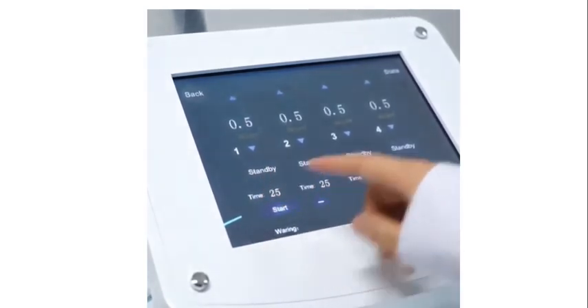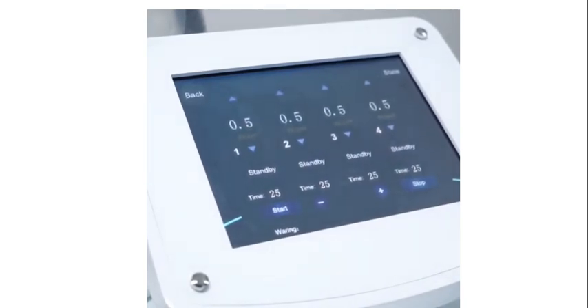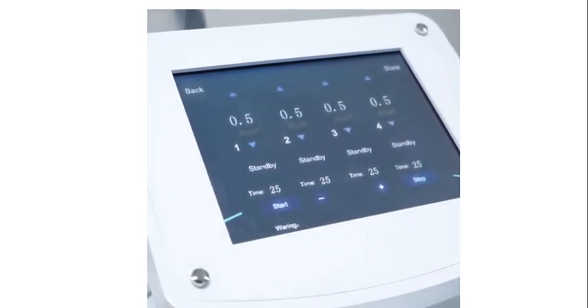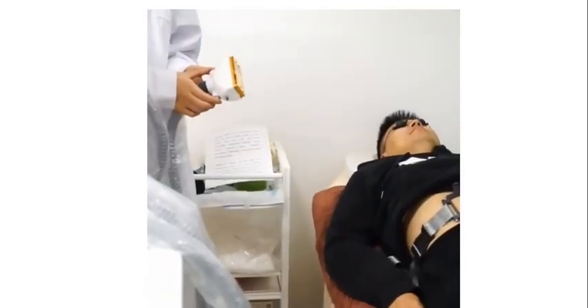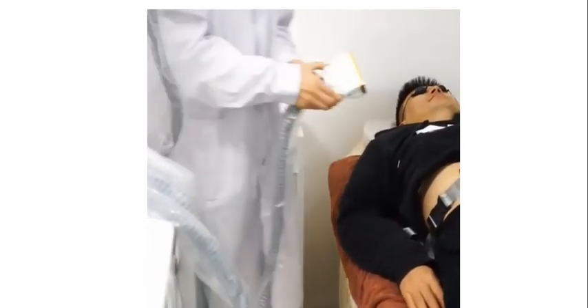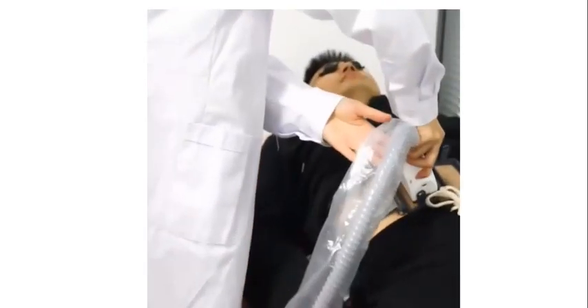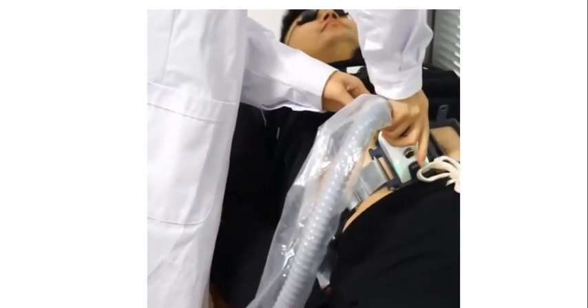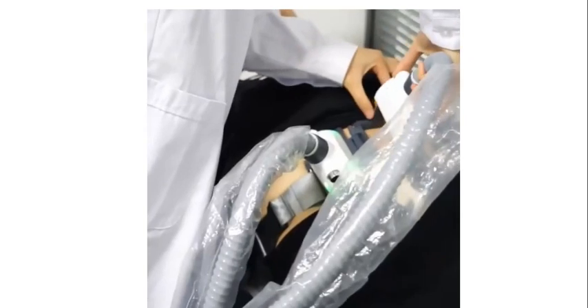Time means treatment time and it counts down. Generally we set 25 minutes. One to 50 minutes can be adjusted. Now we set handles number one, number two, and number three with their handle connectors.